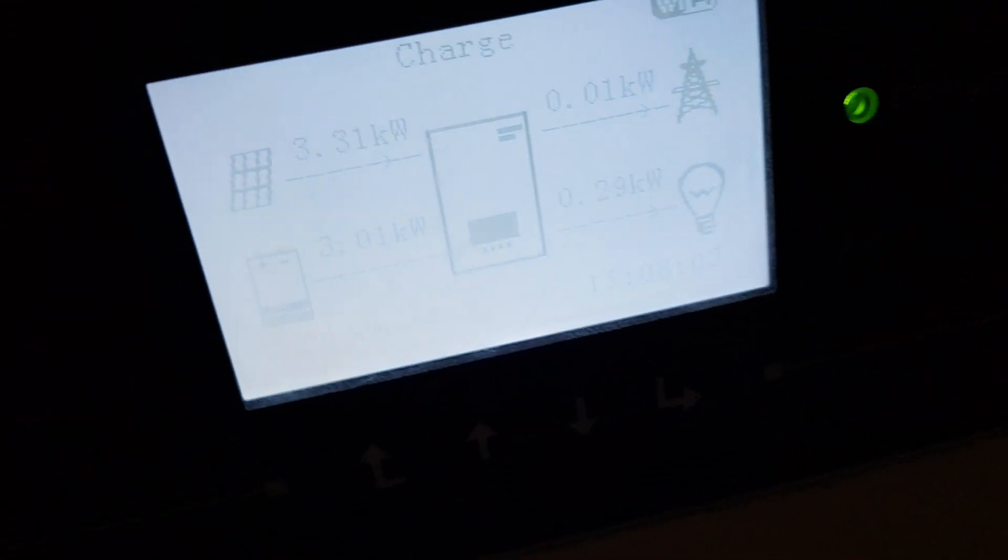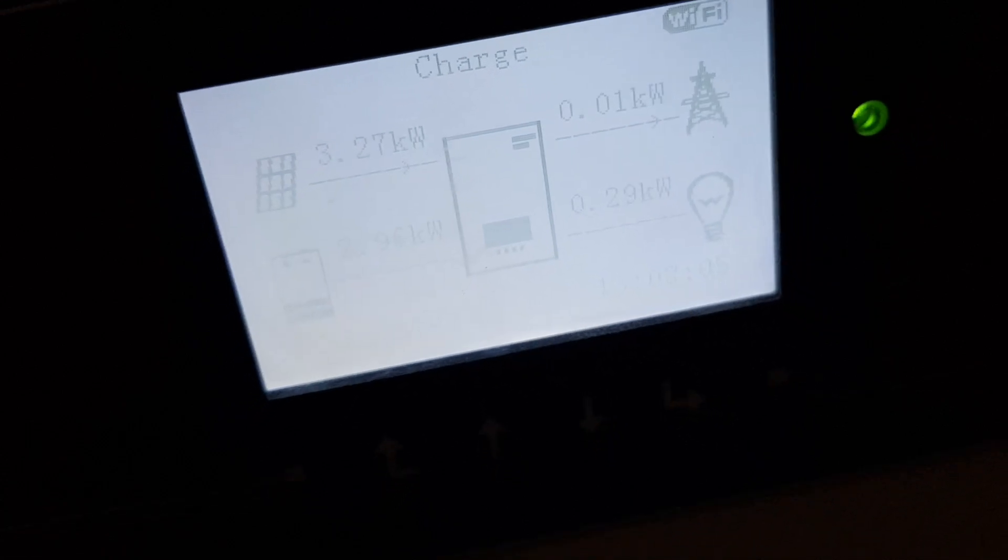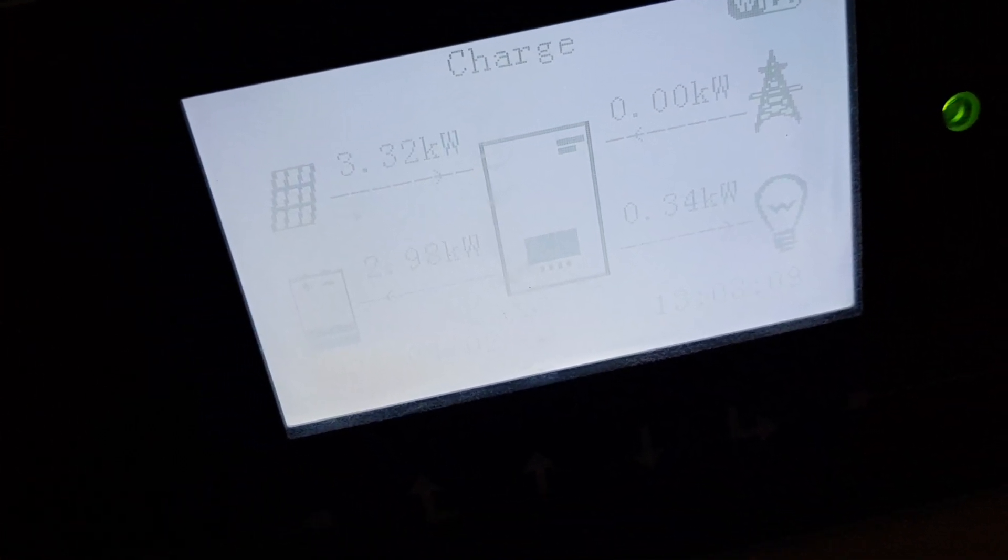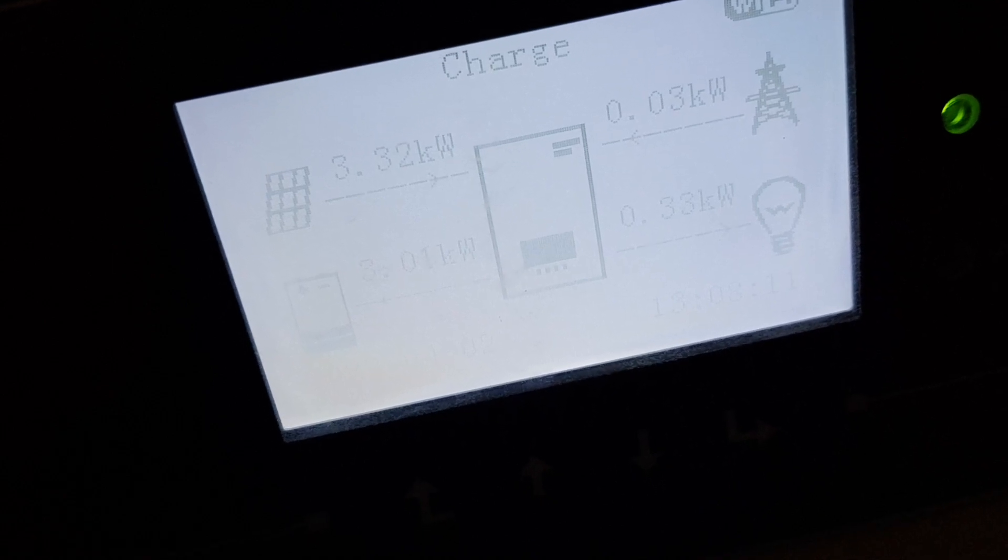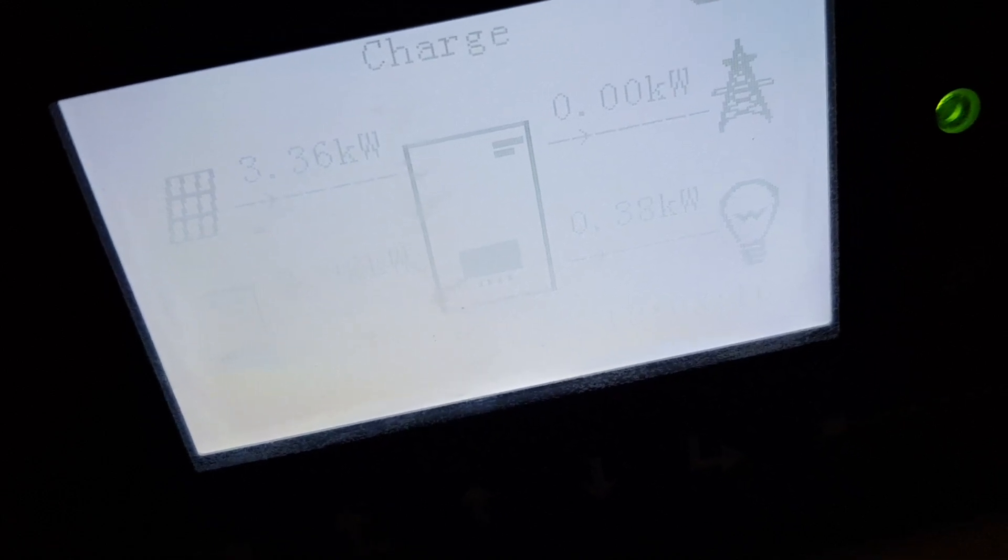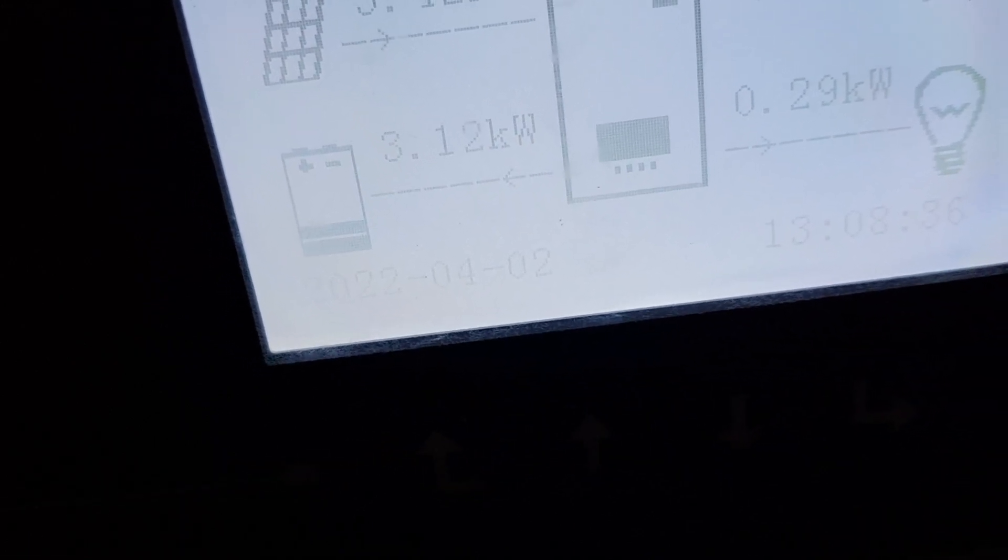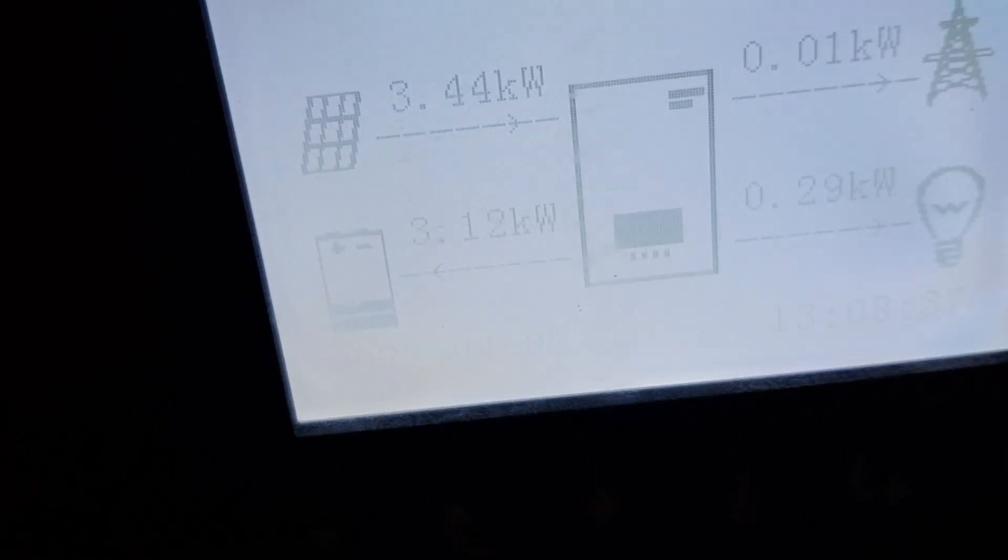This is the inverter here, it's converting the solar charge coming off the roof into battery voltage. We've got 3.31 kilowatts coming off the solar panels, that left icon number one. Then you can see the grid is zero, so we're not using any energy, we're basically living free electric. You can see the actual consumption of the house which is 0.29 kilowatts, and 3.06 kilowatts going into the batteries to charge them.